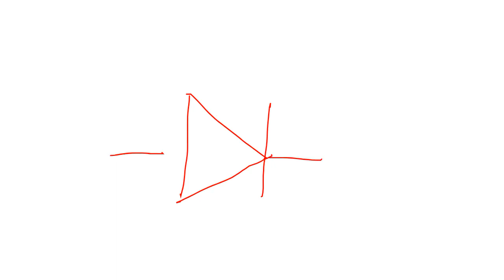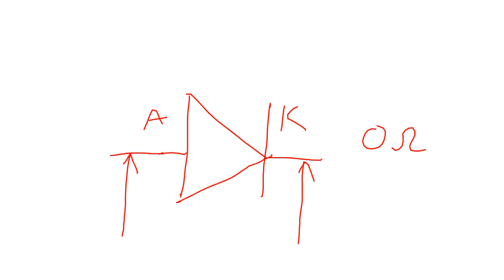So let's draw an SCR, with our anode here and our cathode here. We tell everybody at our training class that an SCR or a diode fails short circuit 99.9% of the time. So the easiest test you can do is get a fluke, put it on resistance, and go from the anode to the cathode. If you get 0 ohms, then your SCR or diode is bad. Do it in both directions, but if it is a short, you're going to get 0 ohms in both directions.